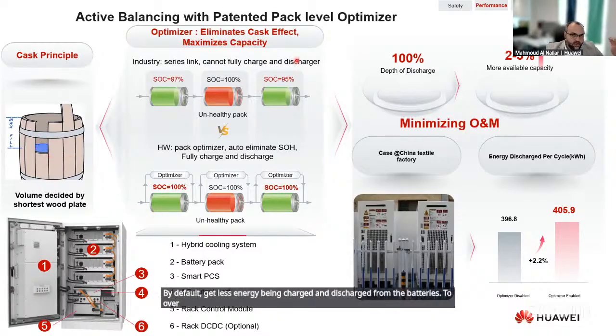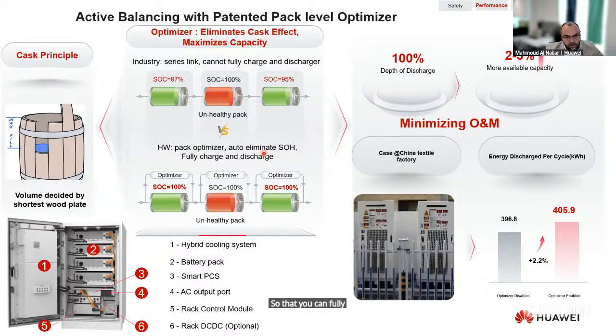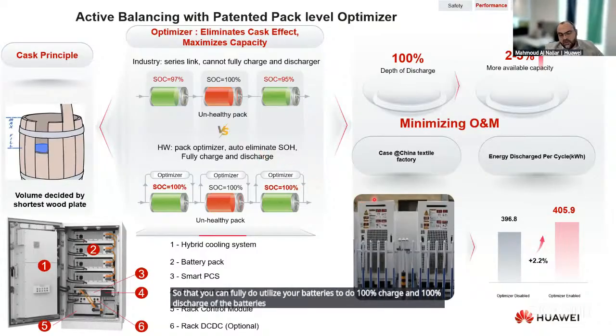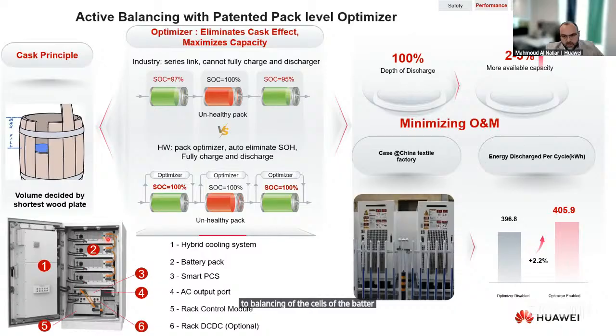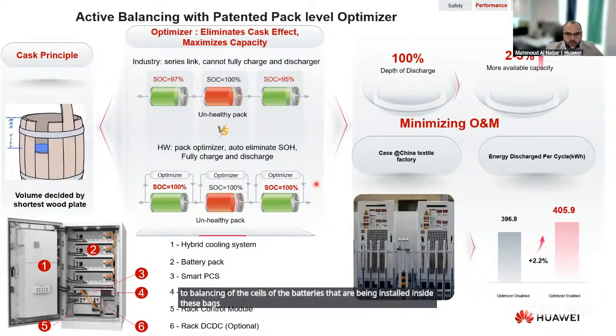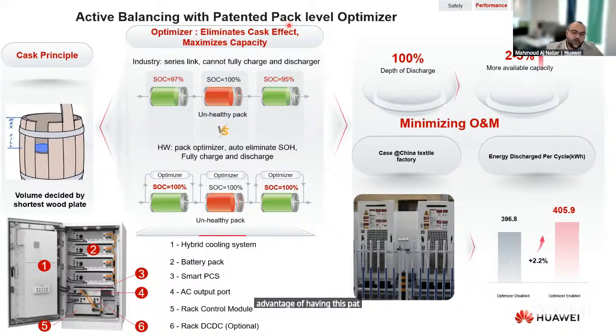To overcome this, we have a patented pack level optimizer that is installed inside each pack, so that you can fully utilize your batteries to do 100% charge and 100% discharge. It also gave us the capability to do active balancing, which will automatically and continuously balance the cells of the batteries installed inside these packs, to omit the need to shut down the system and balance the cells and the packs at least twice a year. So this is also another advantage of having this patented pack level optimizer on the packs.